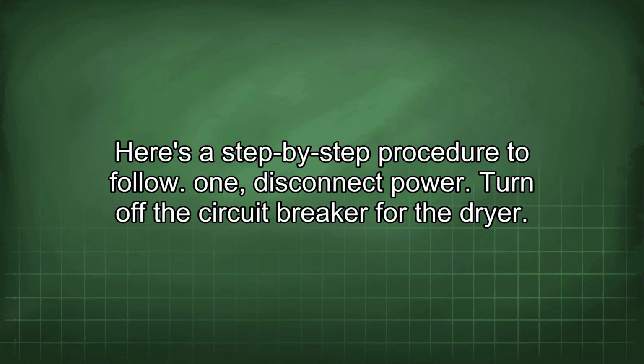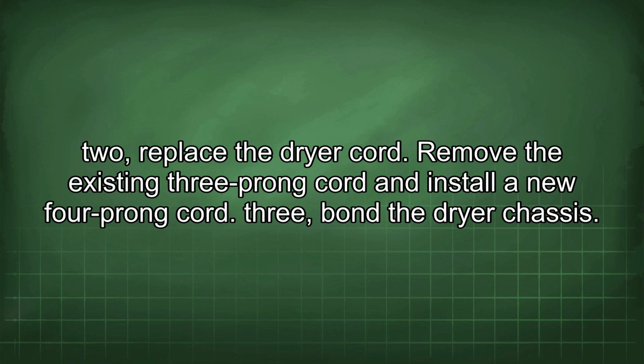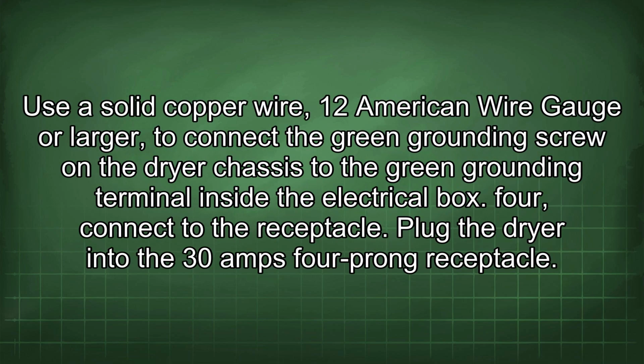Here's a step-by-step procedure to follow. 1. Disconnect power. Turn off the circuit breaker for the dryer. 2. Replace the dryer cord. Remove the existing 3-prong cord and install a new 4-prong cord. 3. Bond the dryer chassis. Use a solid copper wire, 12 American wire gauge or larger, to connect the green grounding screw in the dryer chassis to the green grounding terminal inside the electrical box.